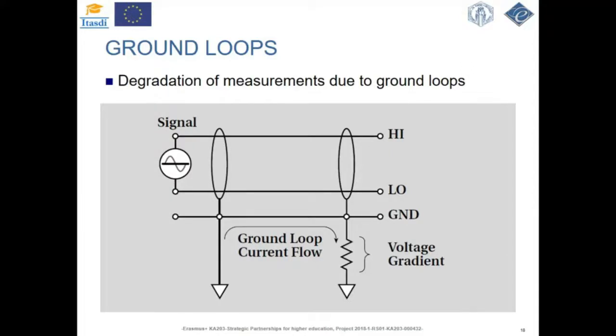On the other hand, there should be no problems as long as the chassis is used as a central grounding point for all other sensors and all other equipment. When instruments, sensors, and other components of the data acquisition system are plugged into the power outlet at different physical locations in a given facility, their chassis can be at slightly different ground potential. The resulting voltage between these different grounds can cause current to flow through the cable shields or other parts of the ground system. This will result in the formation of a ground loop, which is given here on the figure. So this is a ground loop.